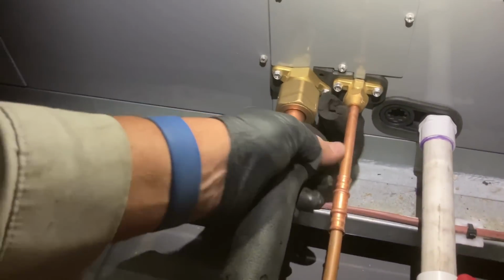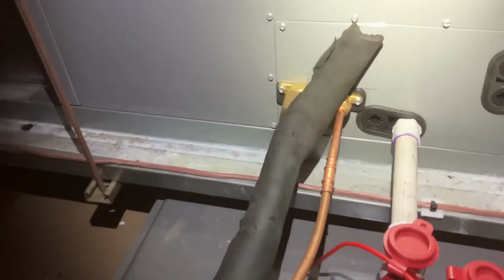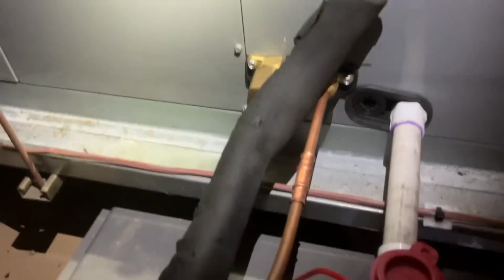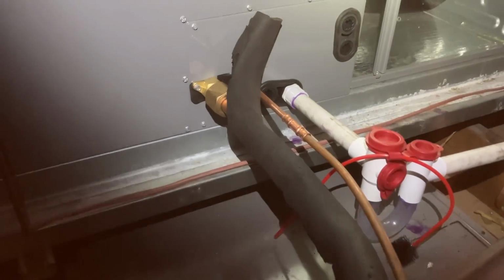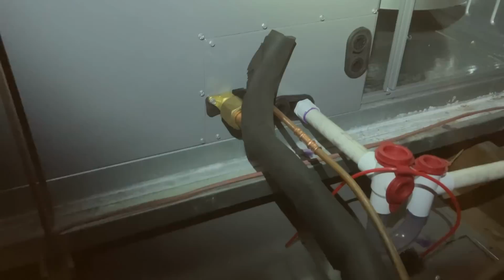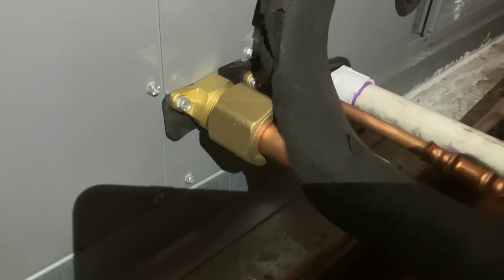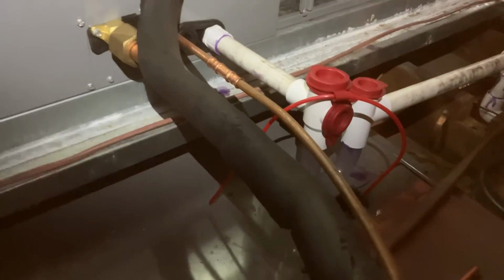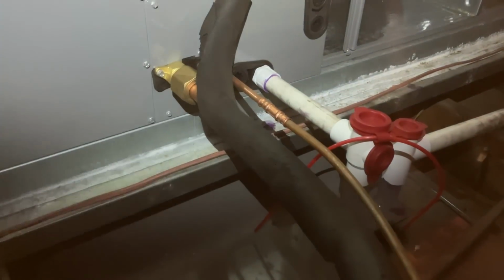You know what? I think this is going to be the first ever heat pump or central AC system that we've ever installed without having to get the brazing rig, or nitrogen to flow nitrogen while you're brazing. They have flare connections on the 7/8 and the 3/8, both on the indoor and outdoor unit. We cut off the swedged ends where it would make it a female, so the copper tubing can slide into the fitting like we did right there, right? We used a zoom lock coupling on the 3/8 and a zoom lock coupling on the 7/8. Made our connections without a torch. We reduced liability, burning down the house. You know, some jurisdictions you need fire watch, flame watch.